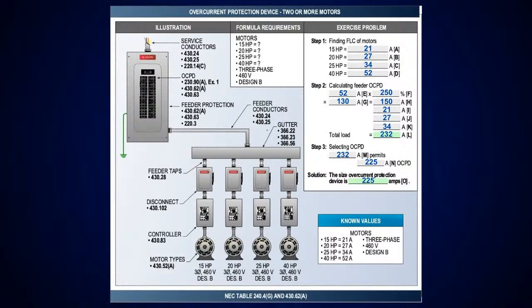You go over to table 430.250. You pick up your 460-volt, come down, pick up your 15 horsepower. Tells you it's good for 21 amps. The 20 horsepower is good for 27. Your 25 horsepower is good for 34 amps. And your 40 horsepower is good for 52 amps.